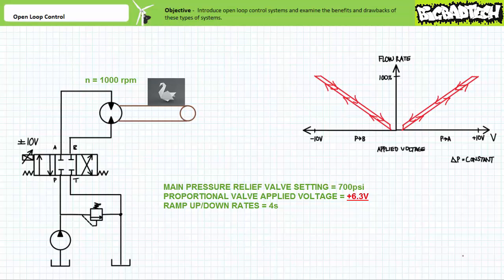Alternatively, a technician can leave the applied voltage setting alone and increase the main pressure relief valve setting such that the differential increases. However, adjusting the main pressure relief valve may not be the wisest course of action, nor even a possibility, given certain components have pressure limits beyond which they catastrophically fail. Pressure, flow, and valve position are all now interrelated means of adjusting this system's input such that the desired output is achieved. Ordinarily independent qualities that respectively influence force, speed, and direction are now tied together, and one cannot talk about one without dragging the other two along.